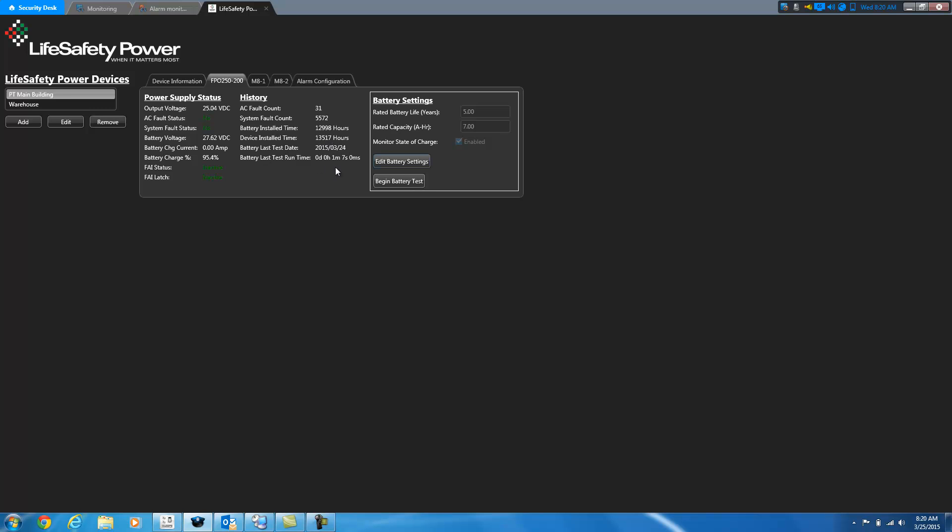Now in order to test the battery, there's a couple of things that you have to have configured. One, under the battery settings here, you need to make sure that you put in the rated battery life, how many years, and the rated battery capacity in amp hours. And you have to have monitor state of charge enabled.